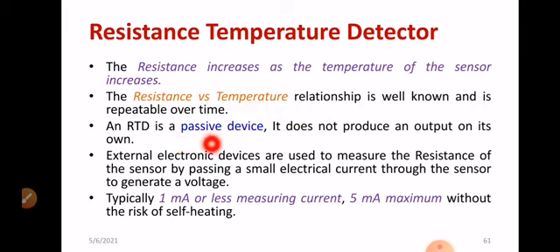Also, R.T.D is a passive device. Why? Because it requires an external source to operate. It does not produce an output on its own. That's why it is known as an active transducer. External electronic devices are used to measure the resistance of the sensor by passing a small electric current through the sensor to generate a certain voltage. Anyway, that particular wire is very important. That is the sensing element. So you will be placing the sensing element within the whole system. Later on, remove that particular wire and measure the resistance. That resistance will be compared with the temperature.